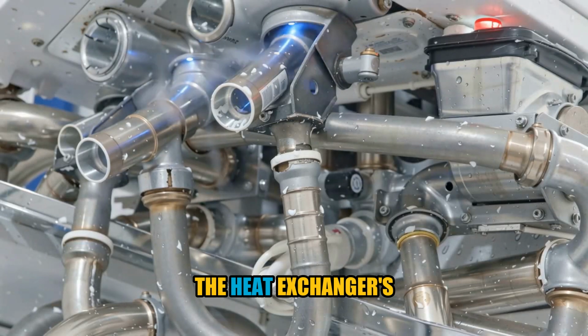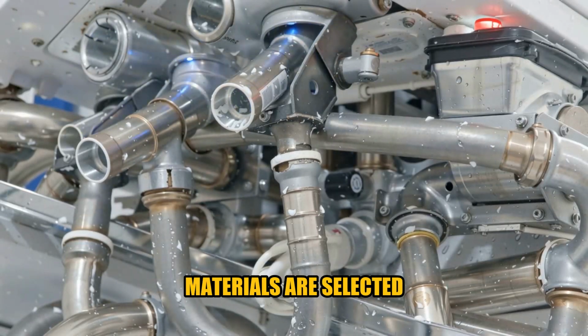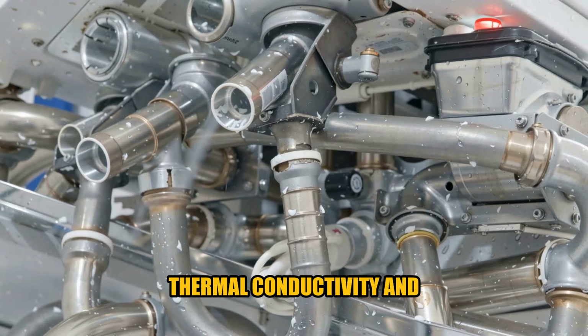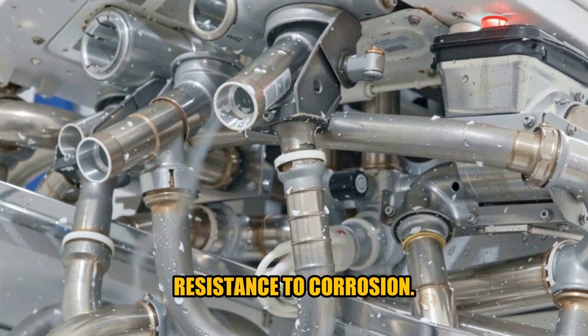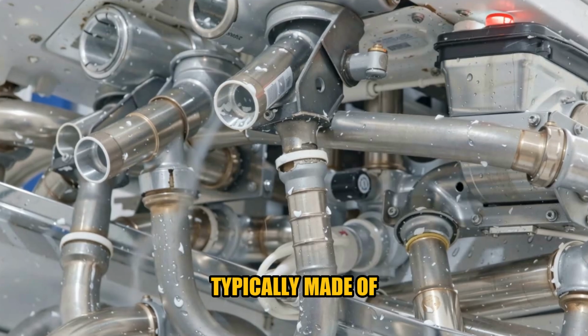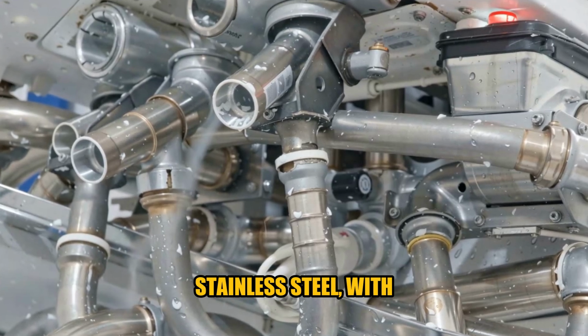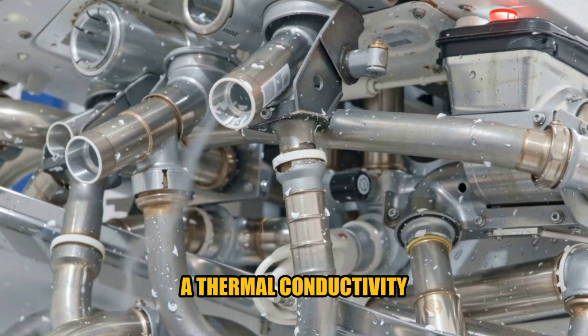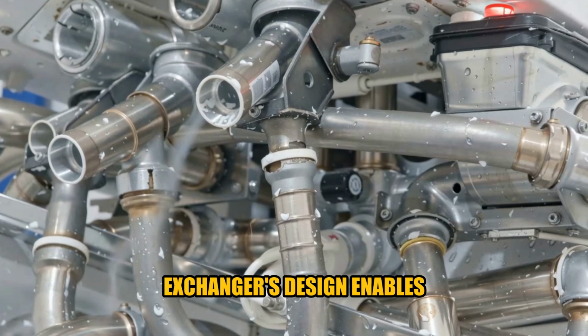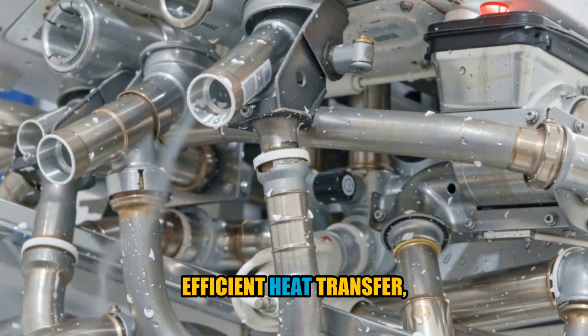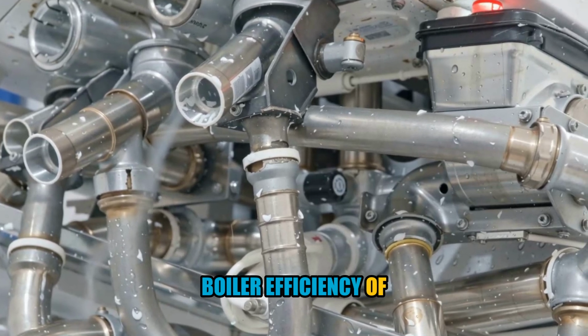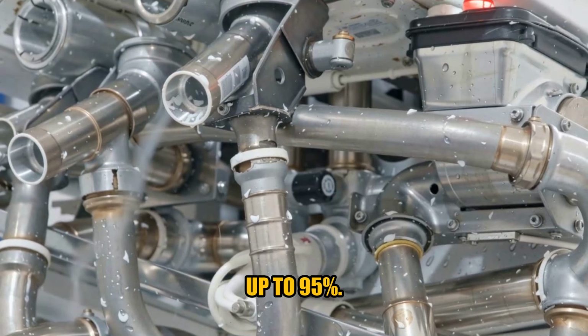The heat exchanger's materials are selected for their high thermal conductivity and resistance to corrosion. The tubes are typically made of stainless steel, with a thermal conductivity of around 15 watts per meter-kelvin. The heat exchanger's design enables efficient heat transfer, resulting in a boiler efficiency of up to 95%.